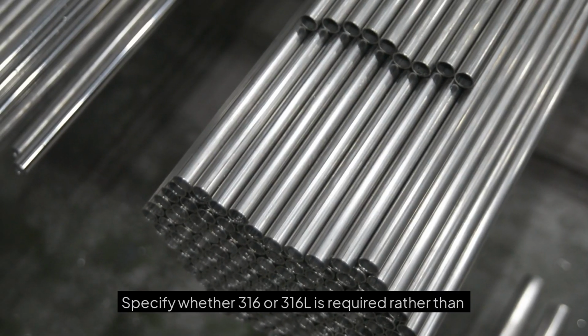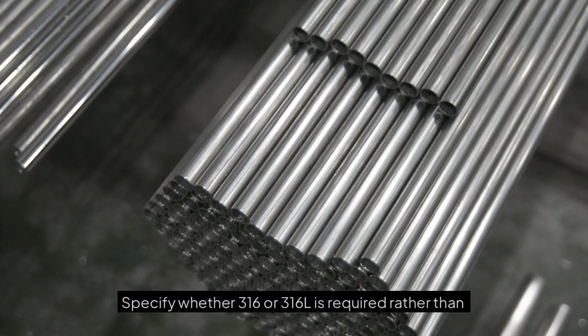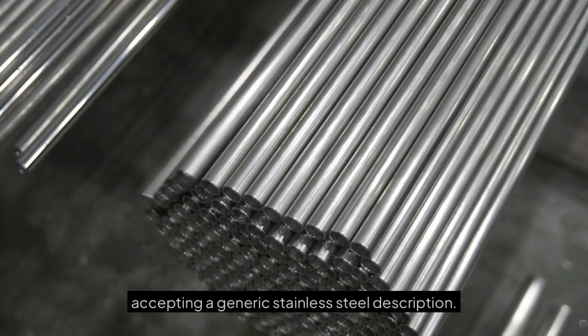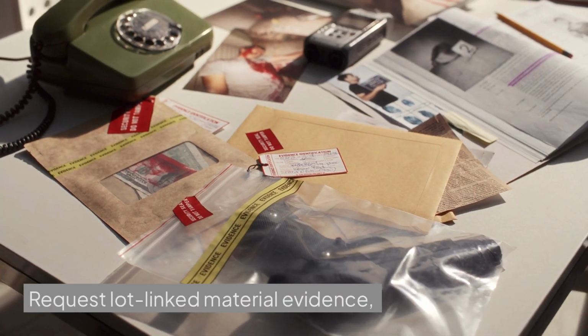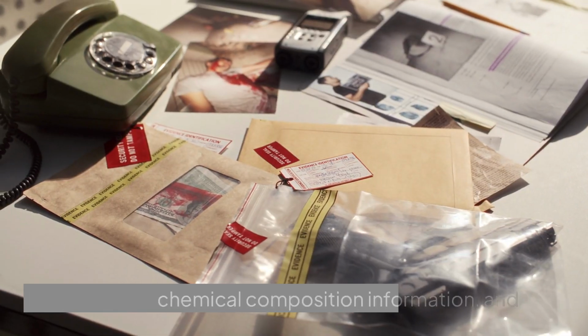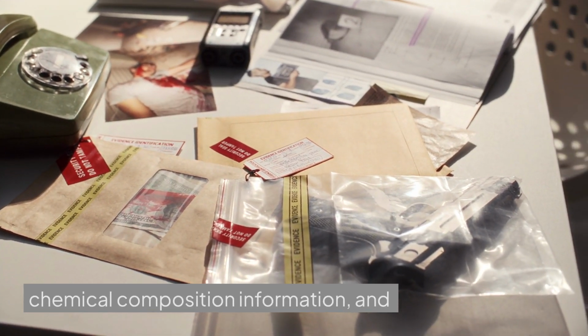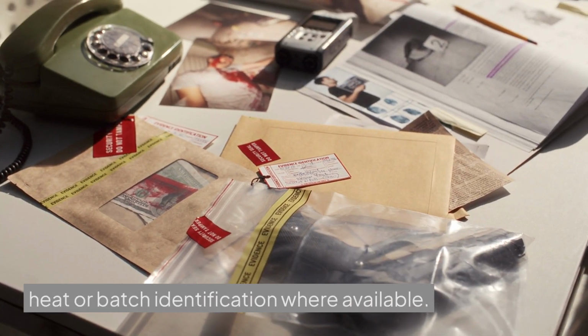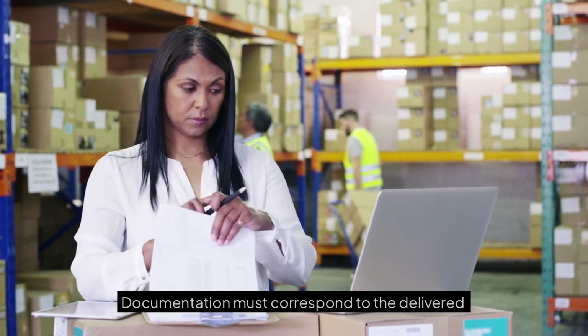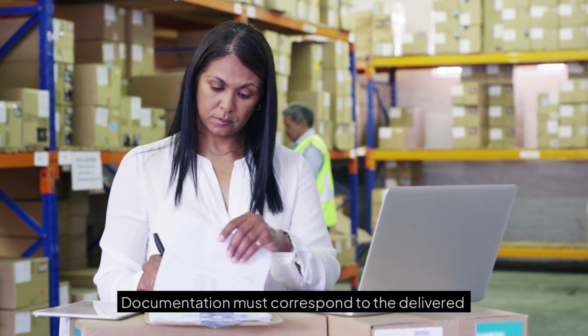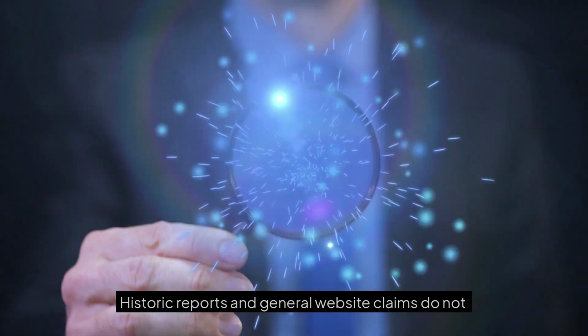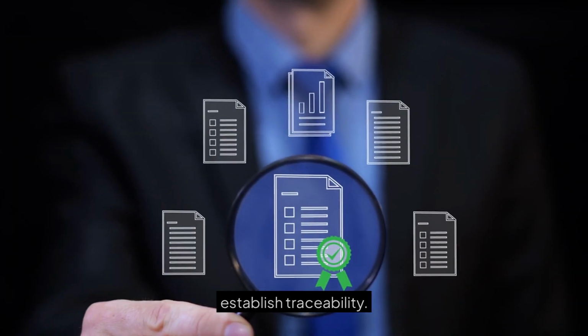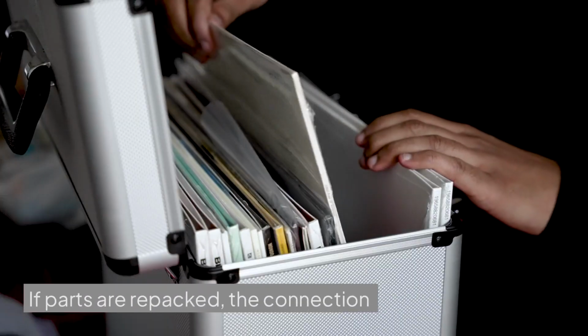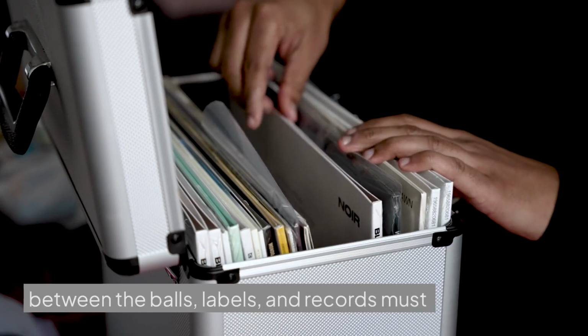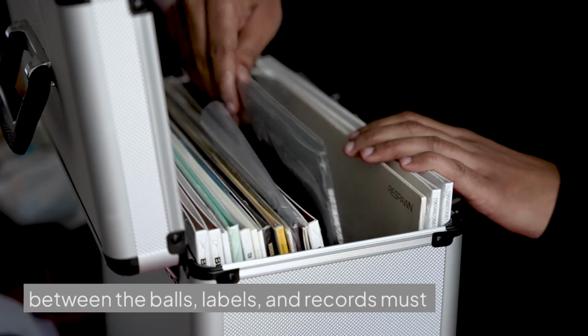Specify whether 316 or 316L is required rather than accepting a generic stainless steel description. Request lot-linked material evidence, chemical composition information, and heat or batch identification where available. Documentation must correspond to the delivered shipment. Historic reports and general website claims do not establish traceability. If parts are repacked, the connection between the balls, labels, and records must remain intact.